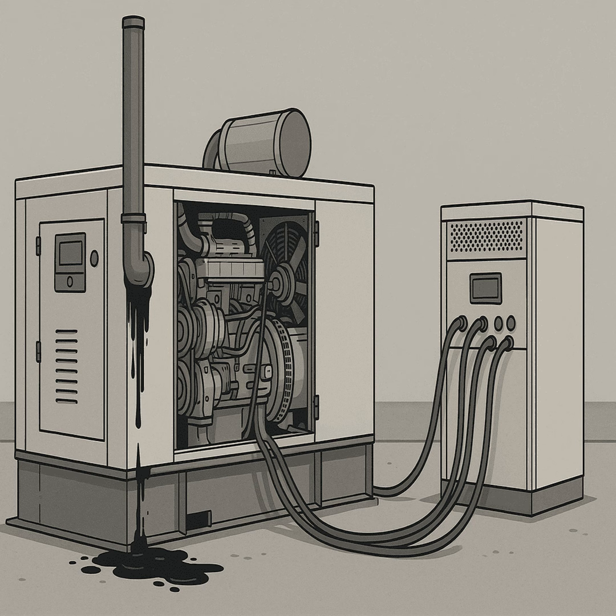It also causes excessive wear on valve guides, and in worst cases, it can lead to damage to the pistons themselves, the piston liners, and the rings, the very core components. You get this buildup of carbon deposits and unburned fuel residues on pretty much all the internal engine parts, and it continues downstream into the exhaust system, affecting mufflers, catalysts, everything. You mentioned piston rings earlier. I've also heard the term glazing connected with wet stacking. That sounds particularly bad. Glazing is a serious consequence.